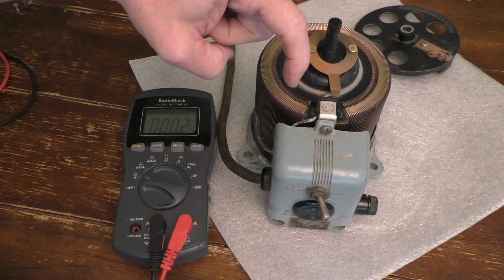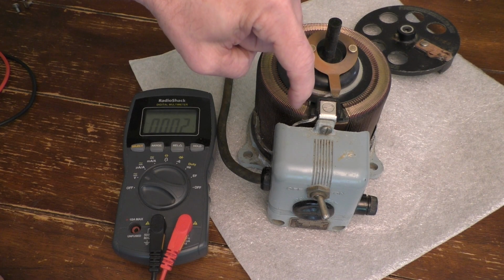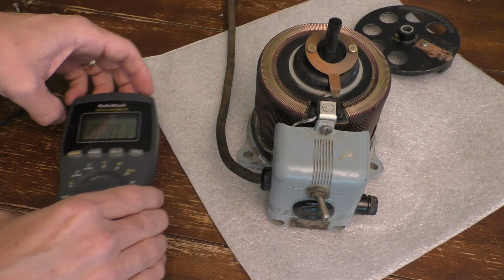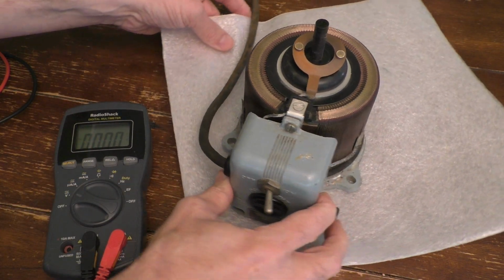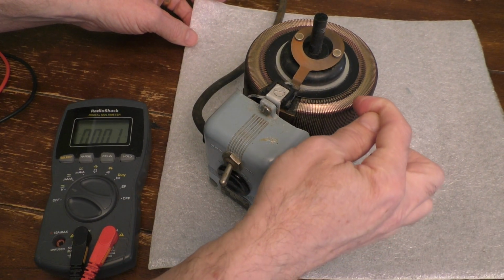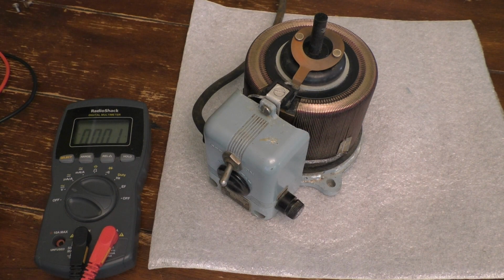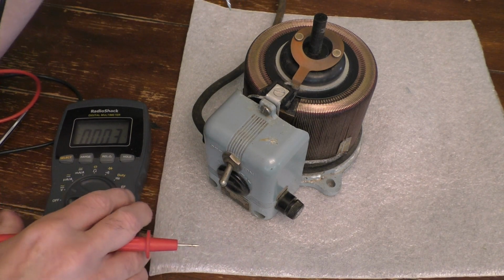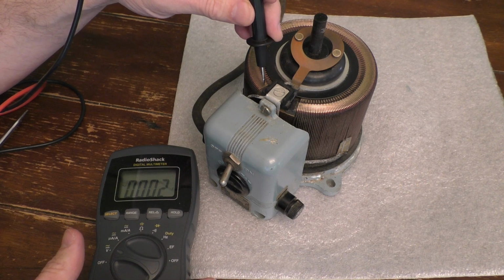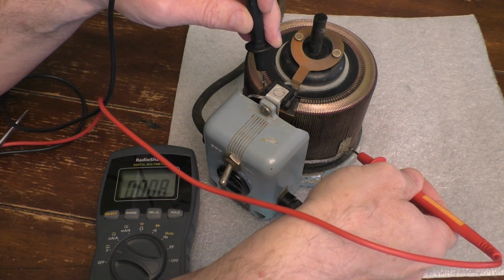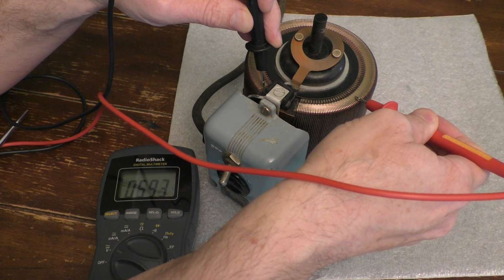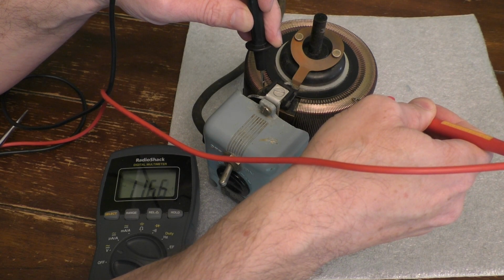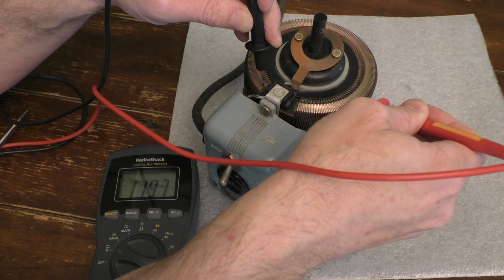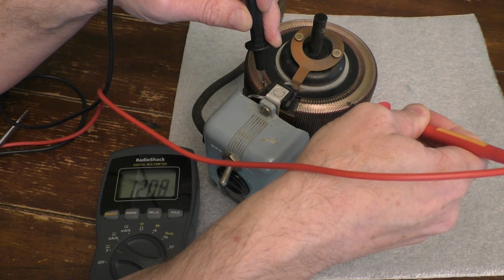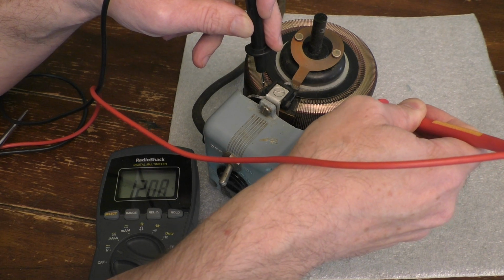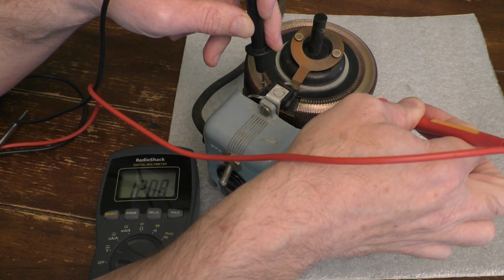there. And so again, terminal 1, the neutral, is connected to the first winding of your coil, which is right over here. And then terminal 2, if I could turn this around, is right here. And so that would be about the connection point right here. And so if I were to put one lead on the terminal 1 here, let's set up the multimeter, just like that. And then the other lead around where terminal 1 or terminal 2 comes in, it should be about 120 volts. Well, let's see if I raise it up a little bit. There, that's 120 volts. So basically what I'm measuring is from the incoming neutral and the incoming hot, which is the 120 volts.